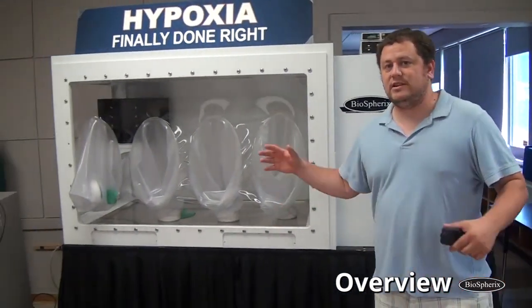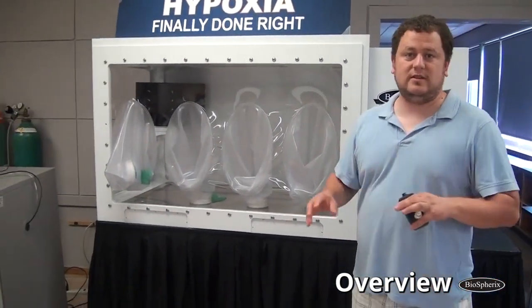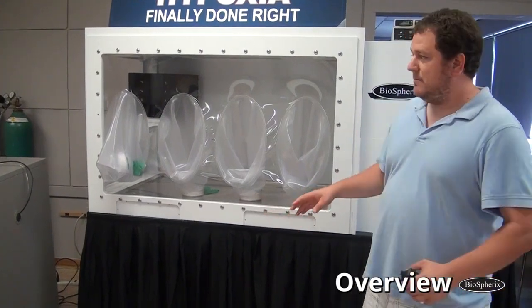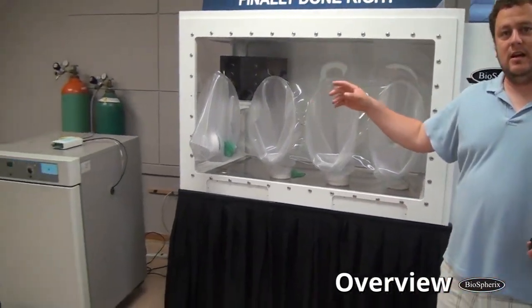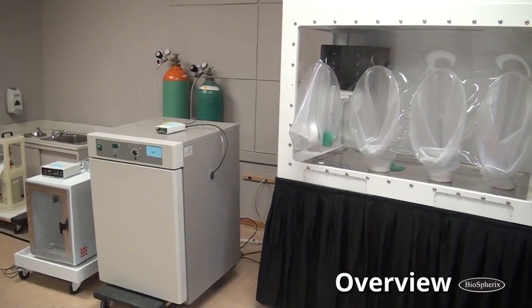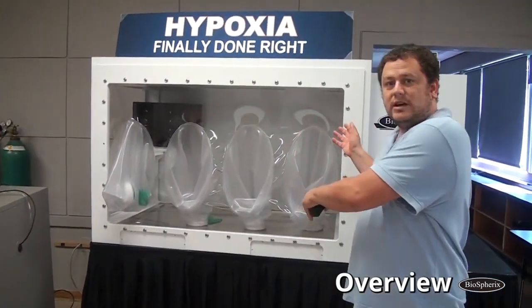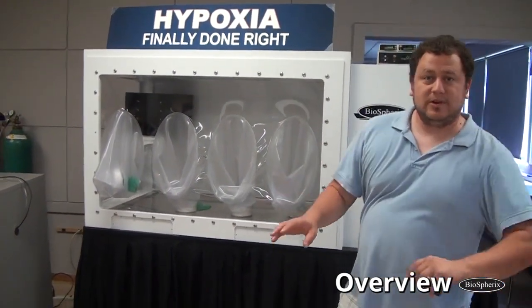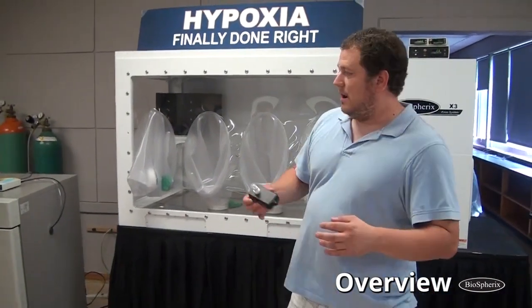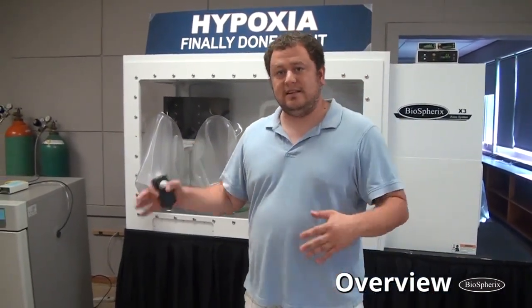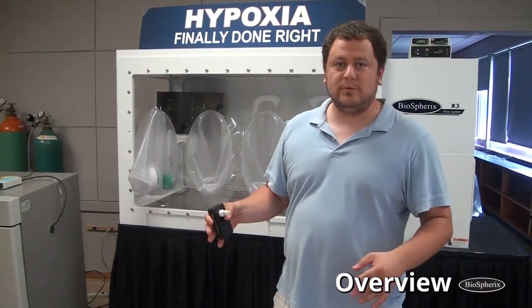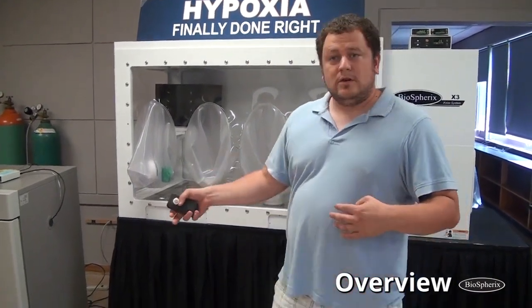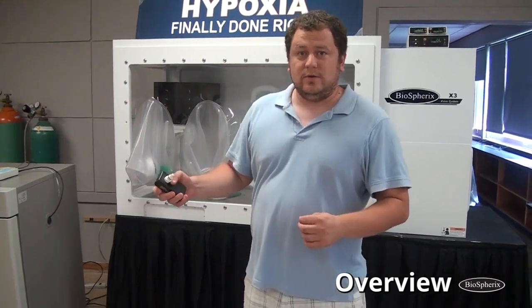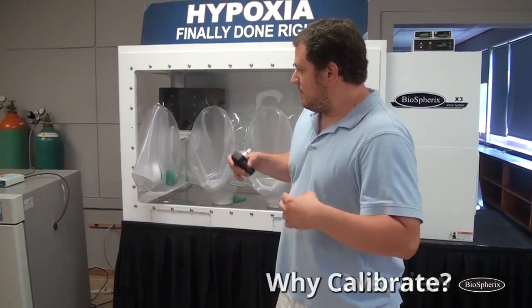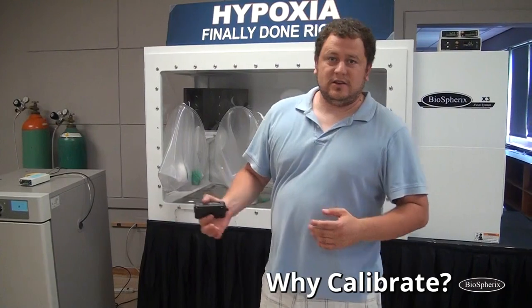So again, you can get tripped up by having different configurations, but the calibration is going to take place exactly the same whether you have a model P360, a model P110, whether you have animal, cell, whether you have the X3 independent line, doesn't matter. Calibration is going to be done exactly the same. I just want to go over kind of the idea behind calibration, why we do it, how often we do it, and then I'm going to show you the different ways that are covered in the manual how to do it. So first off, the idea behind why you have to calibrate.